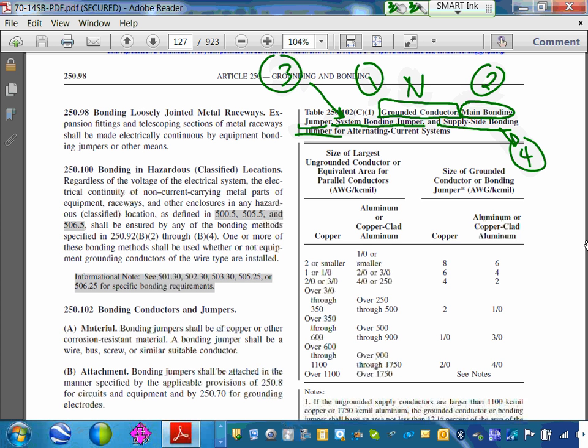So what's the conductor? The phase conductors. What was the phase conductor in each conduit? 600 kcmil. So when you do 600, of course we're in the copper business because we love copper, right? If you're in aluminum, we size based on copper. So good, copper. So 600 will put you in this category, gentlemen, right? Over 350 to 600.